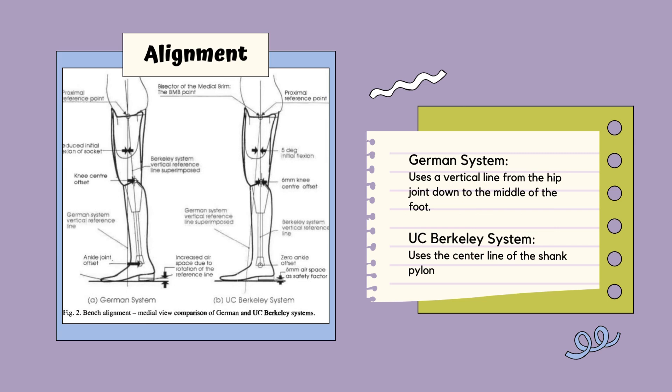Let's now talk about alignment. When setting up a prosthetic leg, professionals use vertical reference lines to ensure stability when weight is applied. There are two systems: the German system and the UC Berkeley system. The German system uses a vertical line from the hip joint down to the middle of the foot. The Berkeley system uses the center line of the shank pylon — the part of the prosthetic leg between the knee and the foot. The UC Berkeley system is more popular because it is simpler and works well with different prosthetic designs.